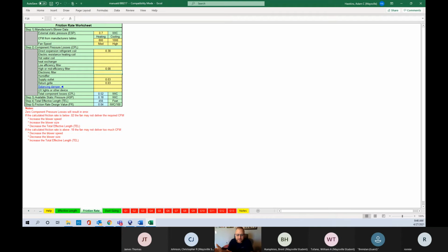In class, the next time when we go through our little layout, we'll do branch sizes, as we're going to see how big of a run I need to move this much air through. So if you look at your little thing here, let's say at a 0.04 static, I need to move 150 CFM. All right, what size round duct do I need to run that in? 8-inch. About 8. About 8-inch.